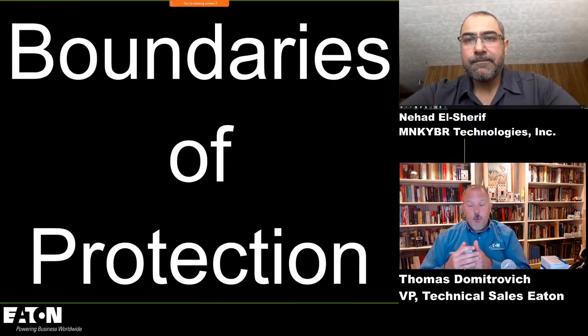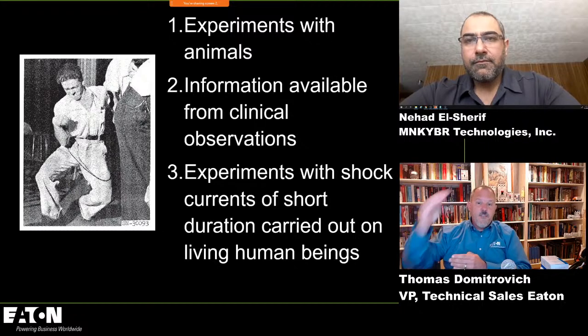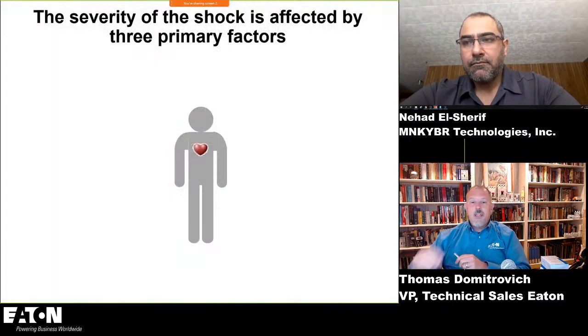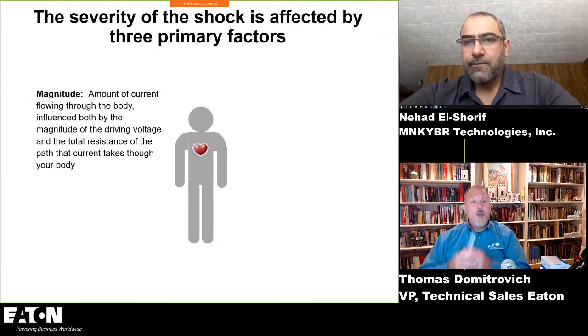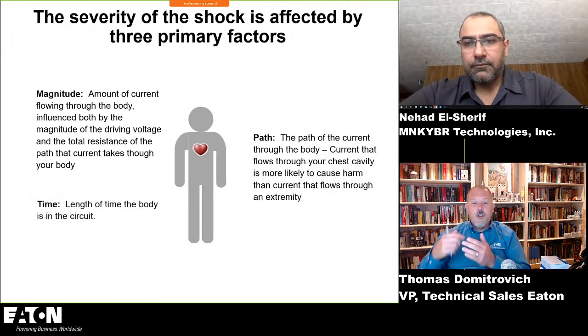All right, Nihad, we're into phase 2 of this discussion: boundaries of protection. So we talked already about the experiments with animals, the information available from clinical observations, etc. We know a lot more about shock today than we ever did before. And we know that there are 3 key things that impact the severity of shock on a human being. The first one is magnitude, and we already talked about that. We talked about the thresholds of 4 to 6 milliamps, and 30 milliamps, other different magnitudes of current, but we didn't talk about how much time that current flows, nor the path that the current would take through the body.